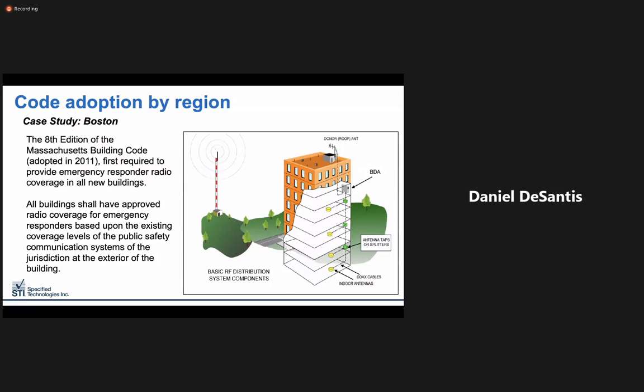Moving north to Boston, found in the 8th edition of the Massachusetts Building Code, adopted in 2011, emergency responder radio systems are required in all new building construction. These requirements can be found in Chapter 9 of the Code of Massachusetts Regulations, or CMR for short. There was a major revision to Chapter 780 of the CMR on April 11, 2014. This code section lays out the parameters for hardware coverage and survivability requirements of the hardware within.